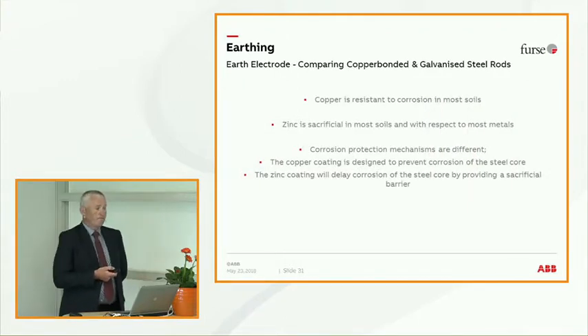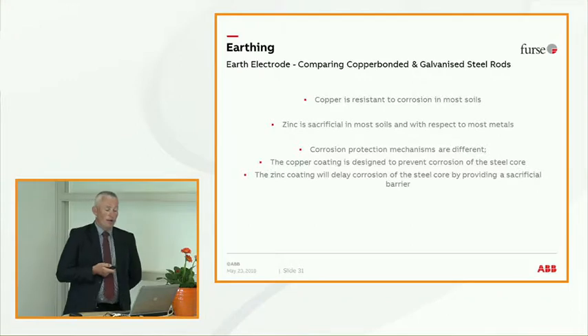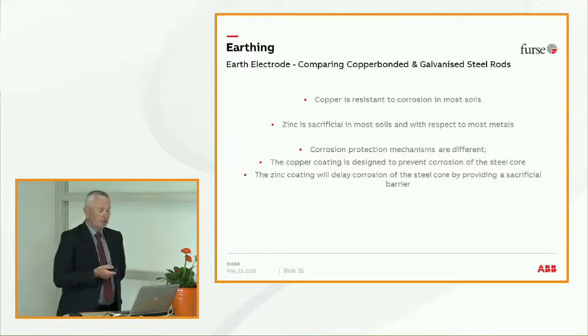One of the problems, and I know this region is a big user of galvanized steel on both the earth rods and the conductor. So if you're using galvanized steel, copper is resistant to corrosion in most soils. The zinc coating on the galvanized steel is sacrificial in most soils. And basically what's going to happen, as the zinc corrodes, it will then start corroding into the steel. So the copper and the copper bonded will last far longer.